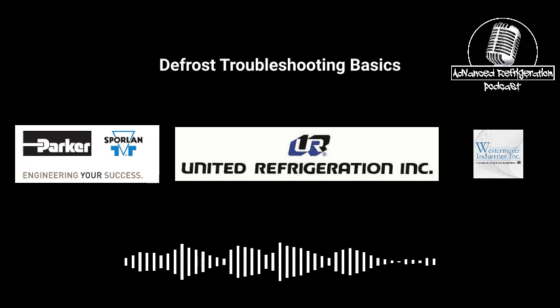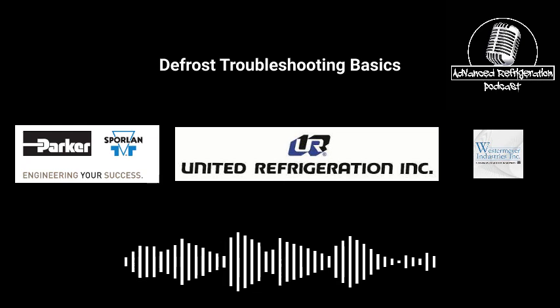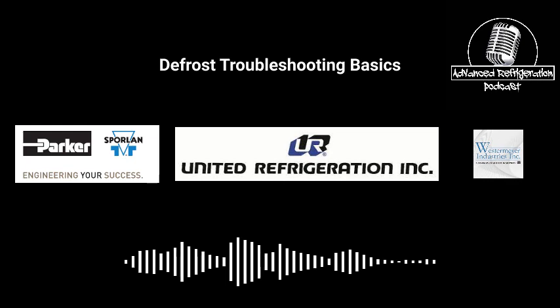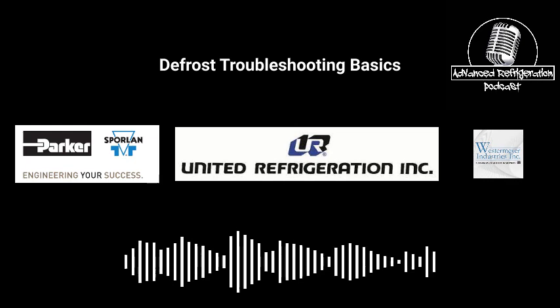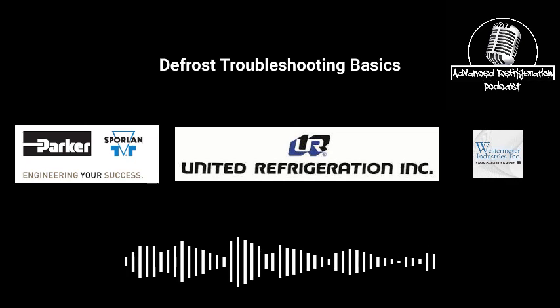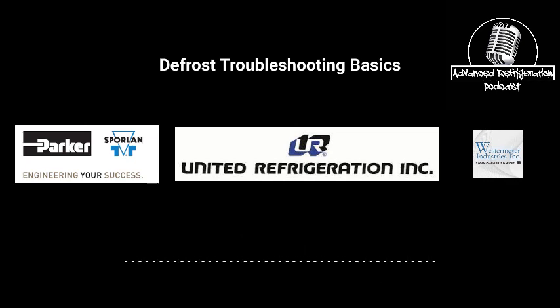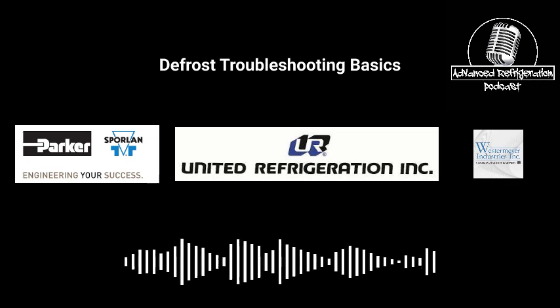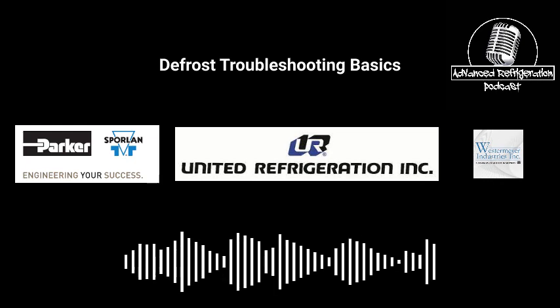Via the liquid line, right? Via the liquid line. So your liquid line sizing gets increased, and then your valve sizing is almost double to triple to sometimes 4 times the size it normally would need to be. I'm assuming this is because of capacity for the expansion valve, right? Yes, just making sure you have enough flow in order to warm that coil up.